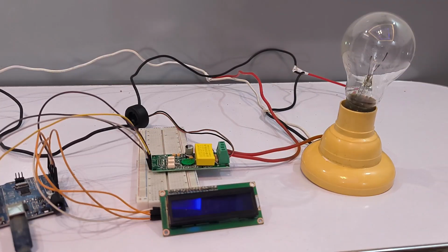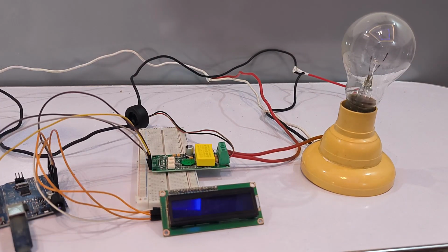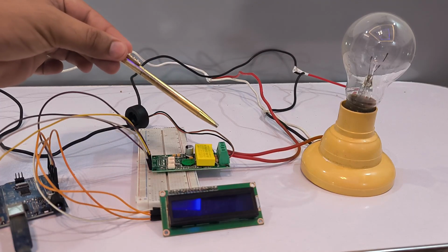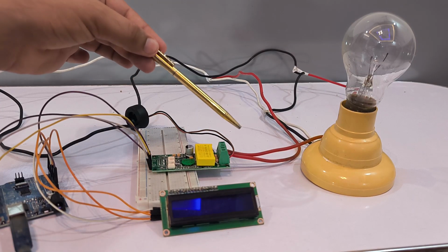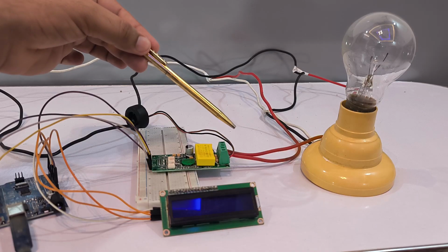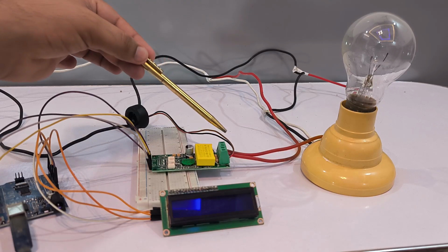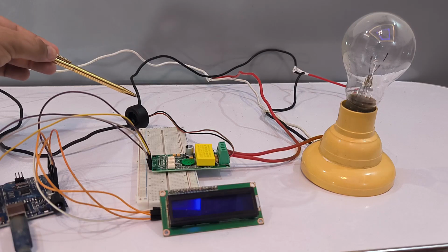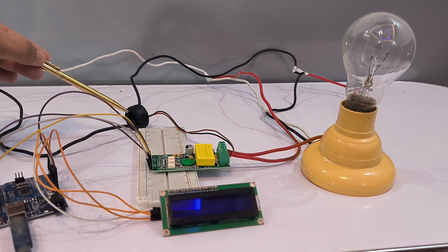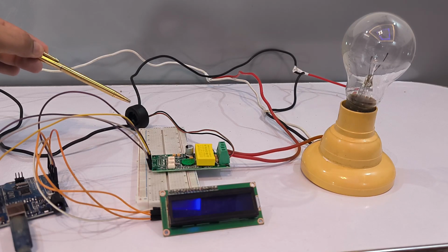To measure the electrical parameters, I first connect a CT sensor to the PZEM-004T module. Then I pass the live wire of the AC load through the center of the CT sensor. This allows the module to measure the current flowing through the wire without making a direct electrical connection.